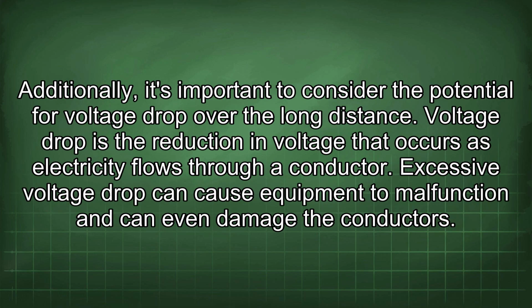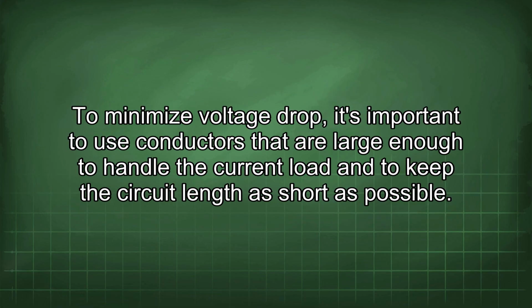Additionally, it's important to consider the potential for voltage drop over the long distance. Voltage drop is the reduction in voltage that occurs as electricity flows through a conductor. Excessive voltage drop can cause equipment to malfunction and can even damage the conductors. To minimize voltage drop, it's important to use conductors that are large enough to handle the current load and to keep the circuit length as short as possible.